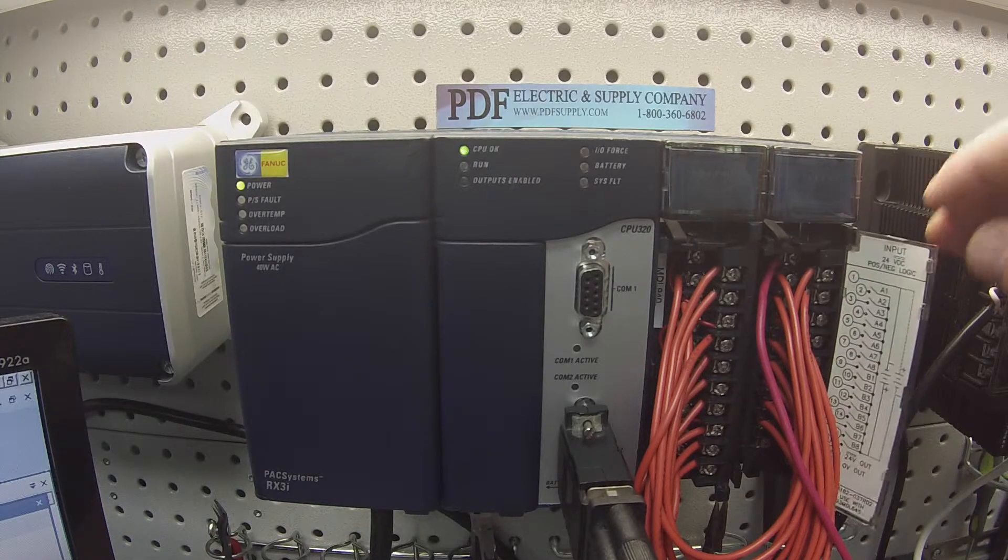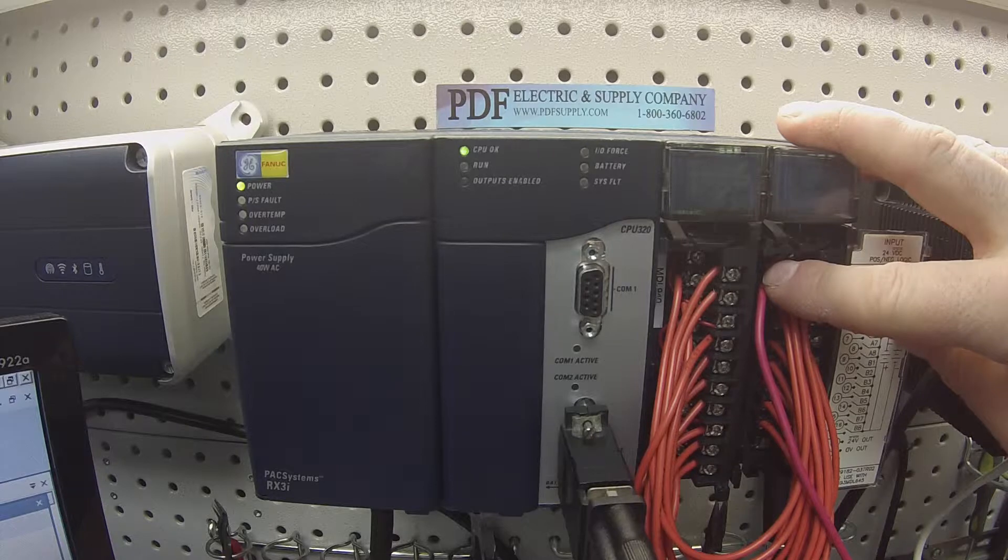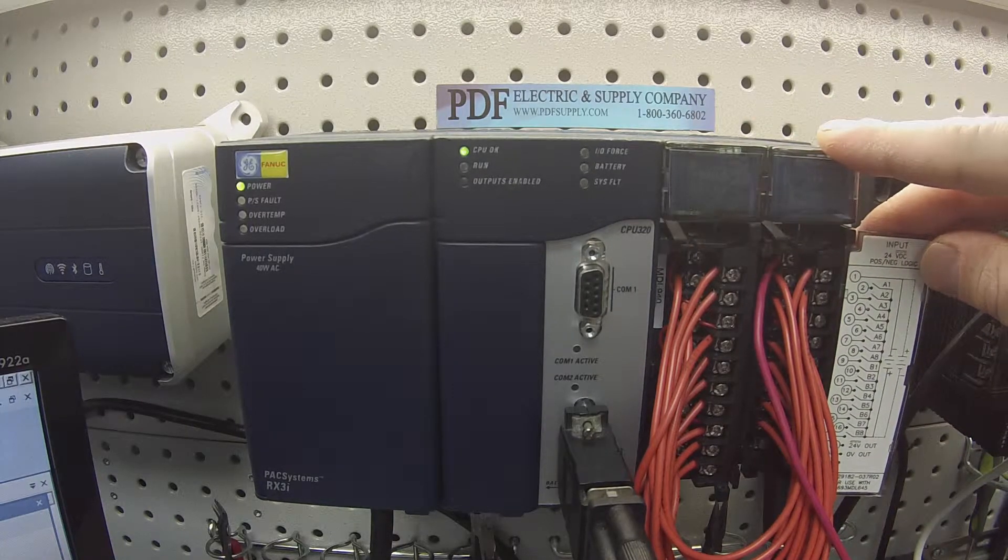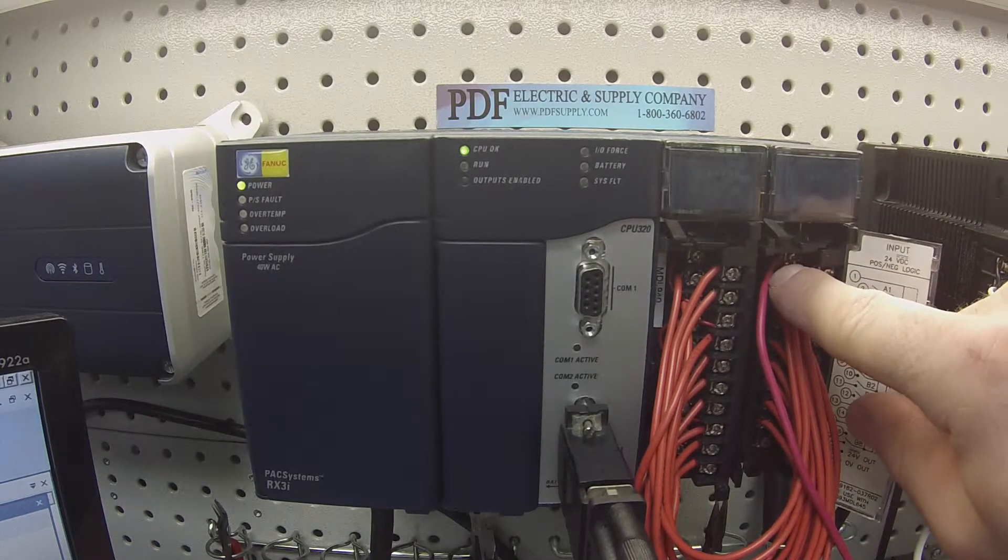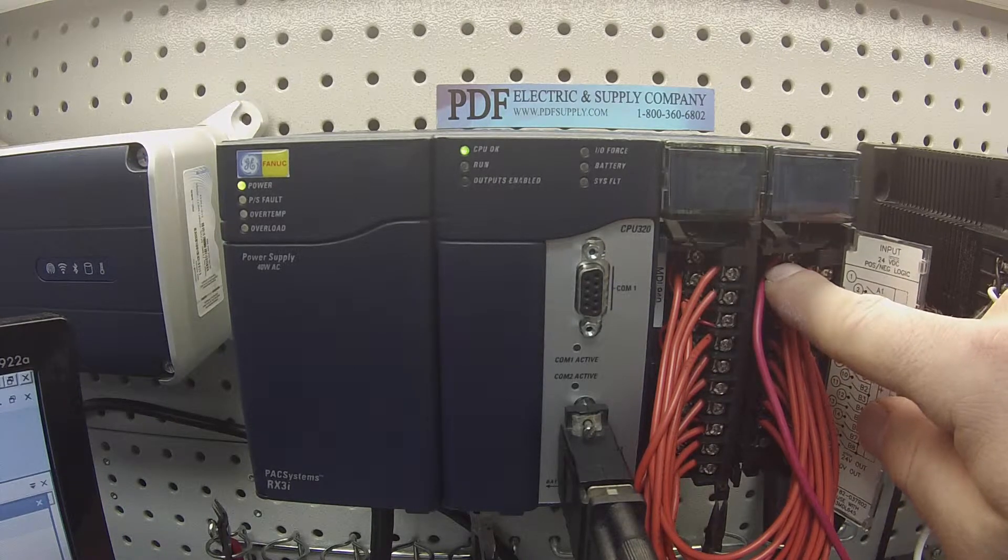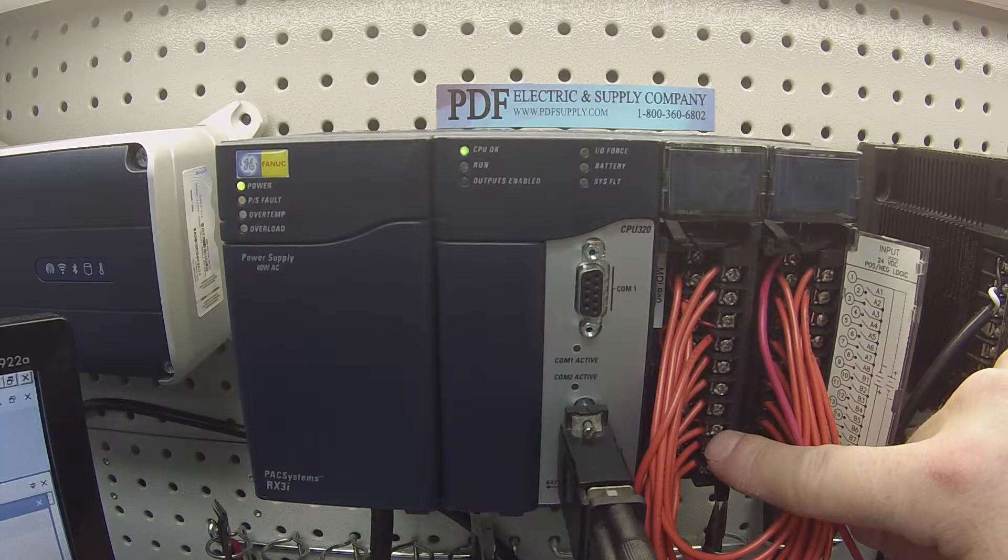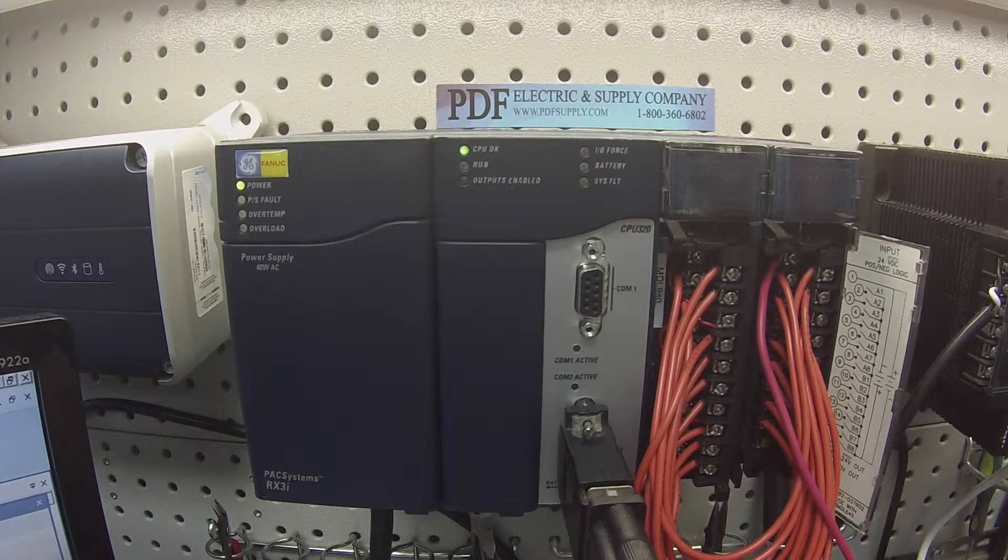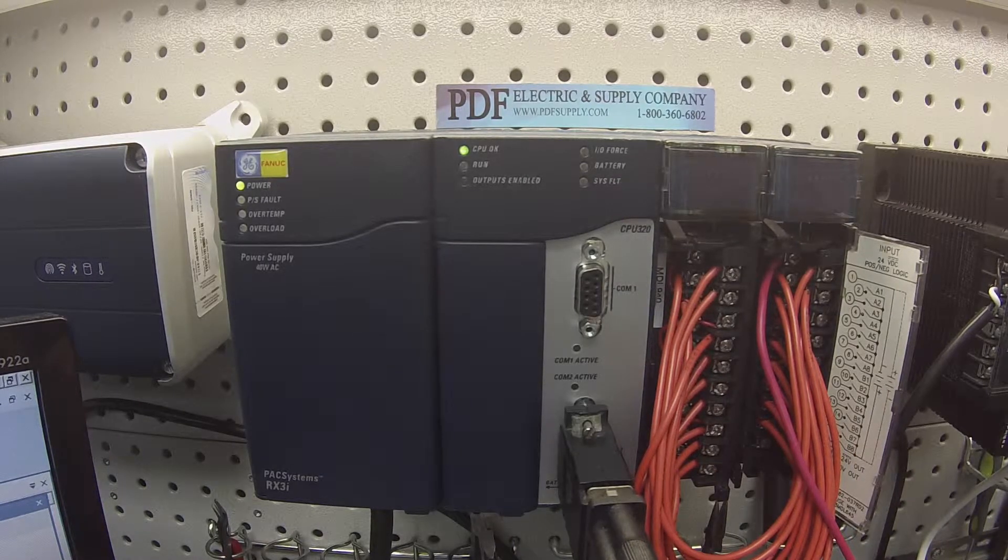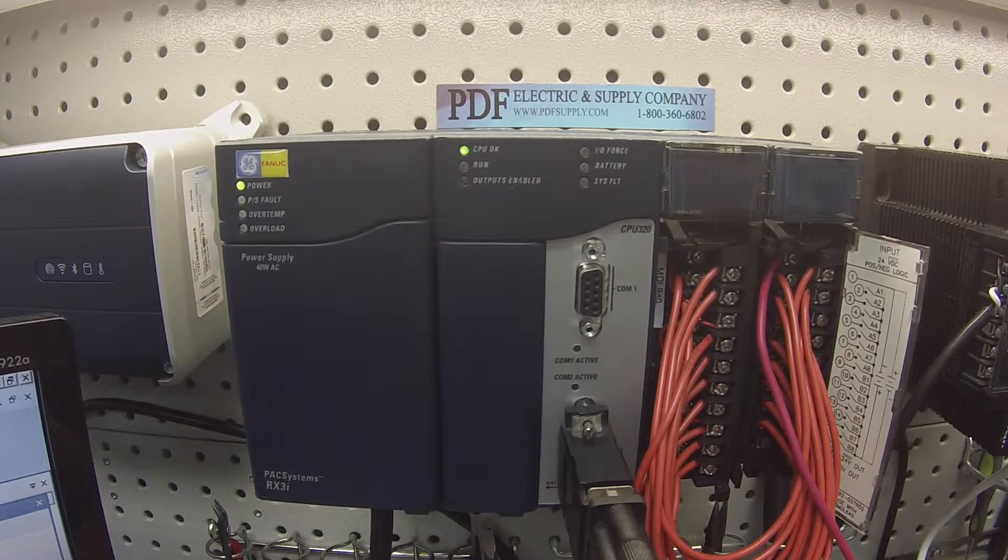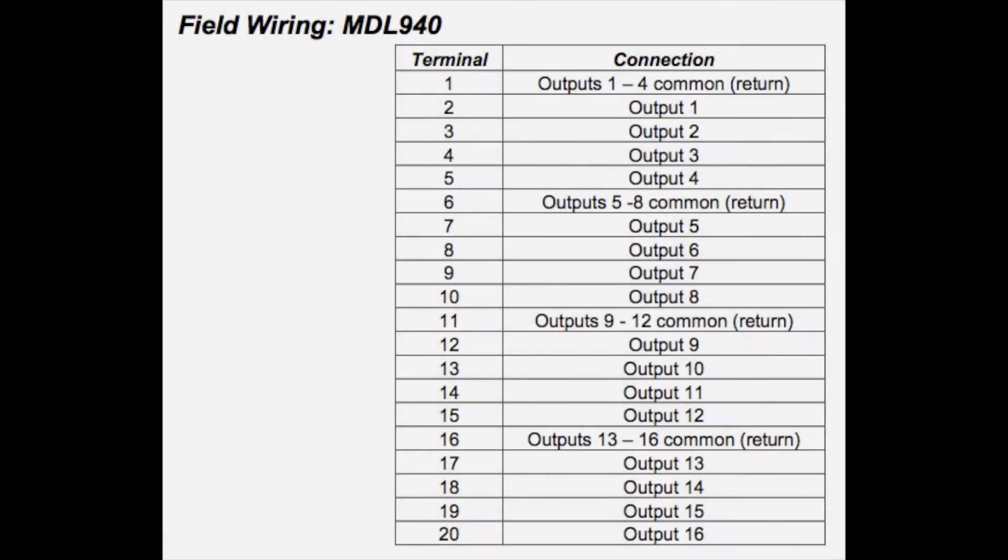What I'm doing now, this doesn't really care how you wire your positive and negative as long as they're opposite each other. But what I've chosen to do on the diagram is to put my positive lead to terminal number one, that would be the top left terminal on the MDL645, 646 input and to terminal 16 on the MDL940 output. So again if you guys are deciding that you want to make a fixture so that you can test your inputs and outputs, you can do that. Now if you don't have or you're not using a fixture, what you can do with the relay output is you can check your wiring diagram.